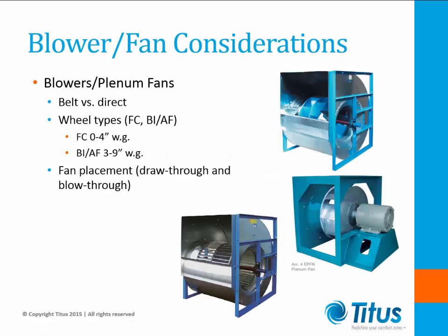There are many types of fans applied to air handlers. The primary differences among them relate to blade configuration, or whether the fan wheel is fully housed or open, and possibly belt or direct driven. Three different types of wheels may be found in the AHUs: a forward curve design, a backward incline, and a backward incline airfoil design. Fans may be oriented in the AHU as blow-through or draw-through configuration. Draw-through typically is known as the most common installation method in an air handling unit.